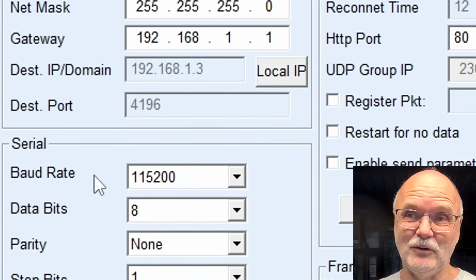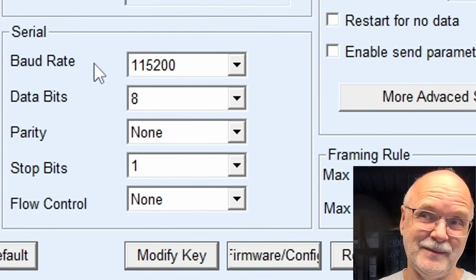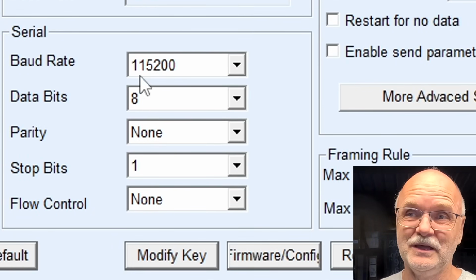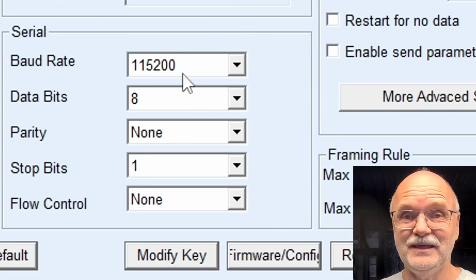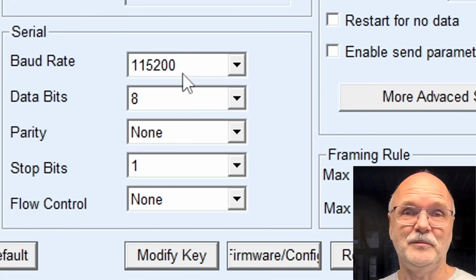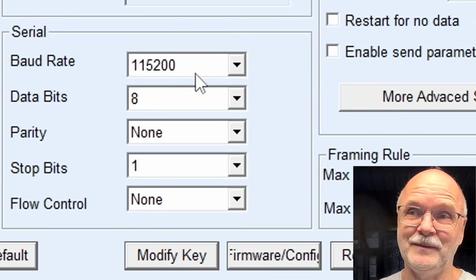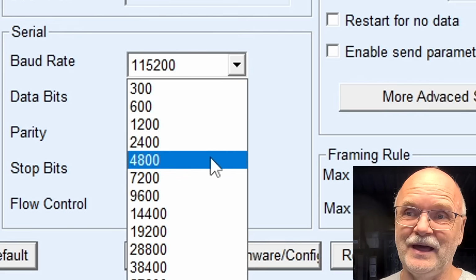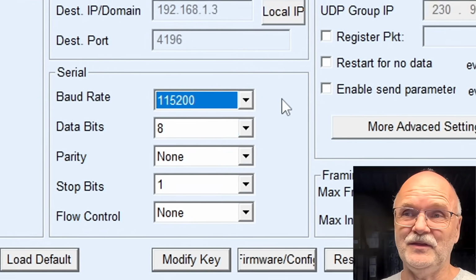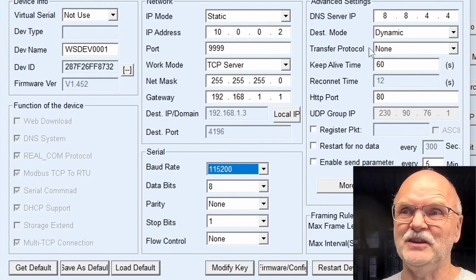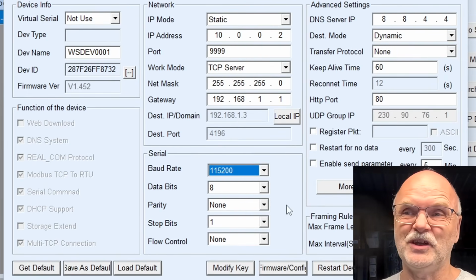Then you set the baud rate for the new Gobel Power BMS for RS232 to 115200. If you use one of the older Gobel Power BMSs or PACE BMSs, you set this one to 9600. These are the only few parameters you need to change. Everything else you don't need to touch at all.